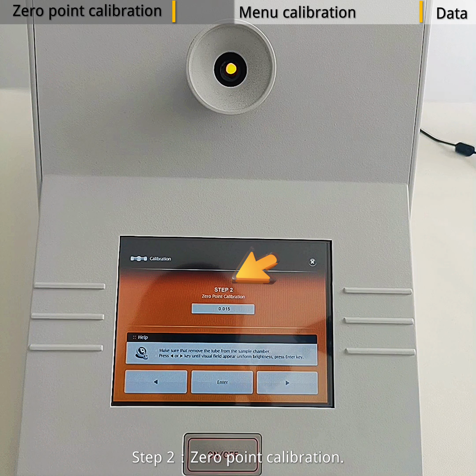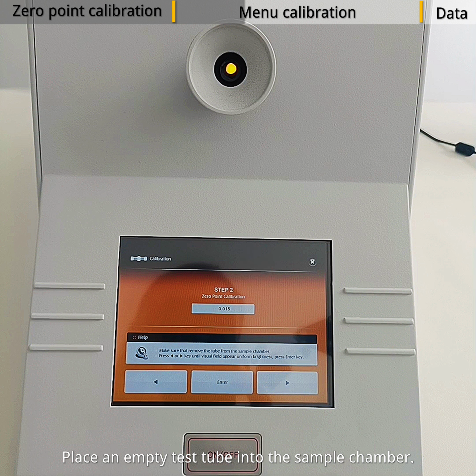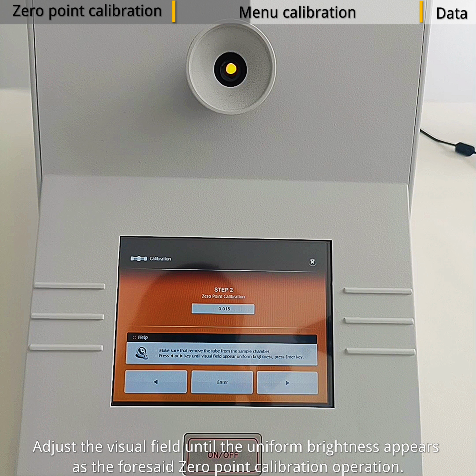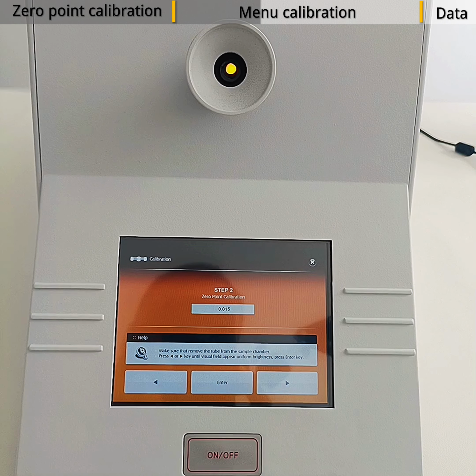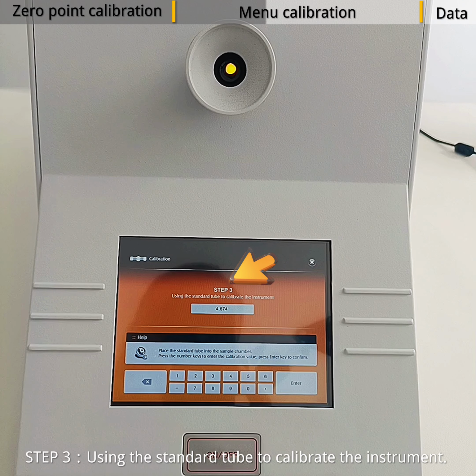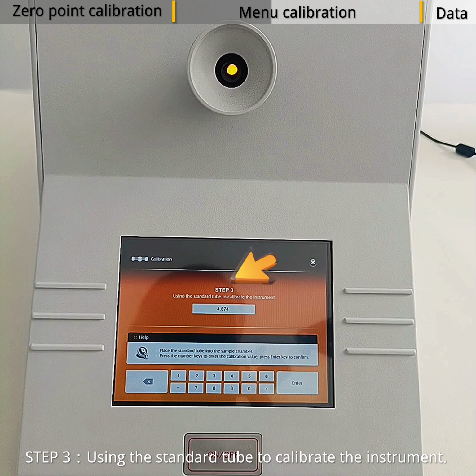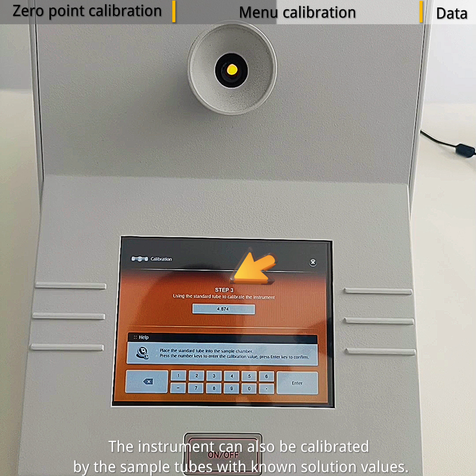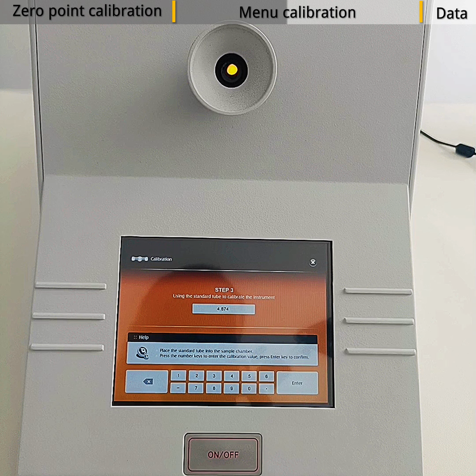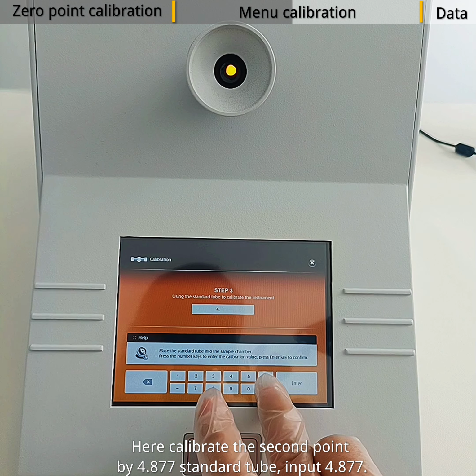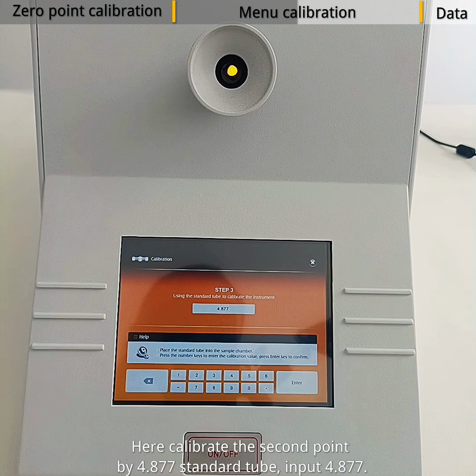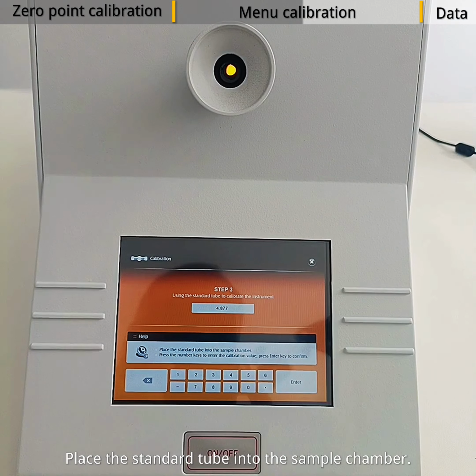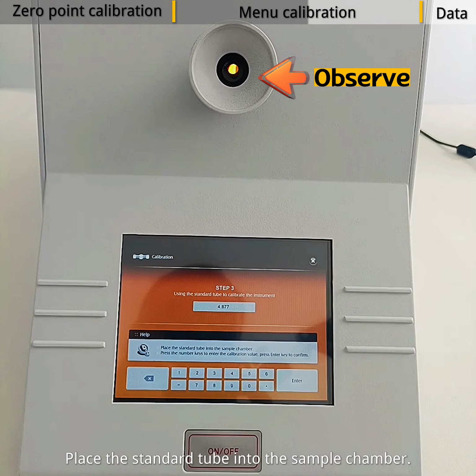Screen shows Step 2, 0-point calibration. Place an empty test tube into the sample chamber. Adjust the visual field until the uniform brightness appears as the 0-point calibration operation. Tap Enter. Screen shows Step 3, using the standard tube to calibrate the instrument. The instrument can also be calibrated by the sample tubes with known solution values. Here calibrate the second point by 4.877 standard tube, input 4.877. Place the standard tube into the sample chamber.